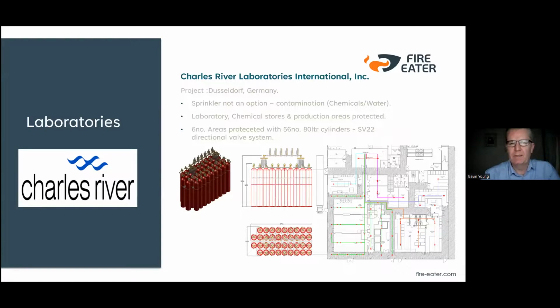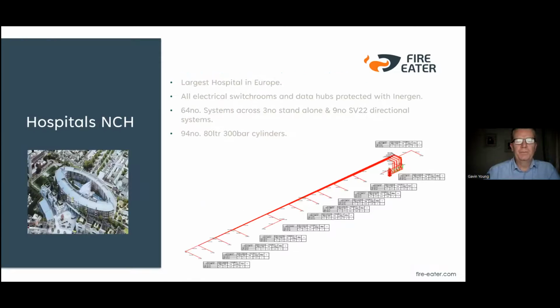This is a project we did in Germany. Sprinklers weren't an option because it was a laboratory. It had chemicals in it. Water would react with the chemicals, and what you didn't want is drainage. So what we did is we zoned particular rooms together and created a system for that. I think it's 64 systems going into the children's hospital. So yeah, we're protecting switch rooms and computer rooms in there. We're doing a lot of directional valve systems for that.